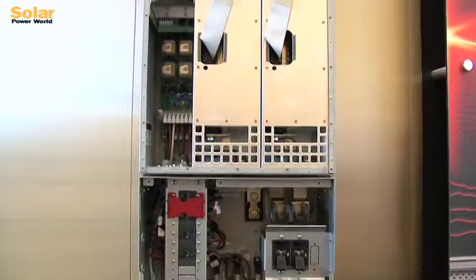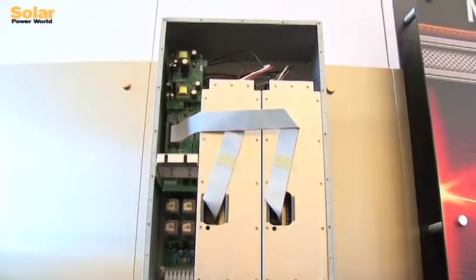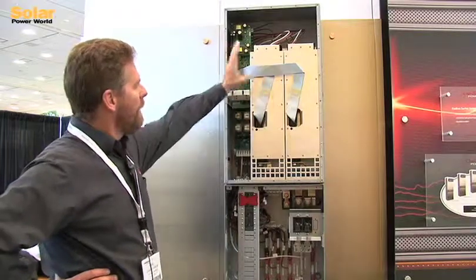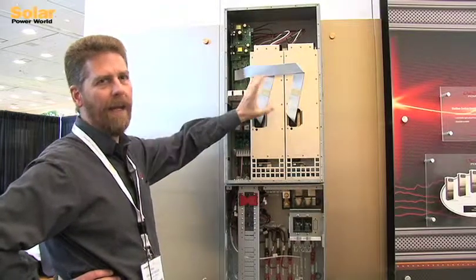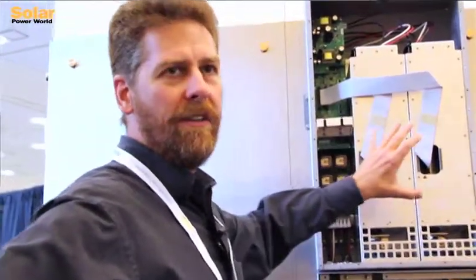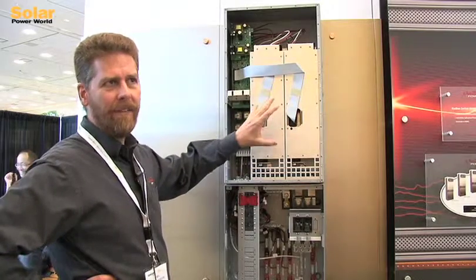This is an example of the internals of the Radian. We have two power modules. Each power module is a 4 kW split-phase full output sine wave module. There's an AC and control board stack that does all of the signal processing, decisions, and commands to the power modules. Each power module can come on in a staged array as loads increase — you can have 10 inverters with 20 modules, and additional modules can come online as loads increase.